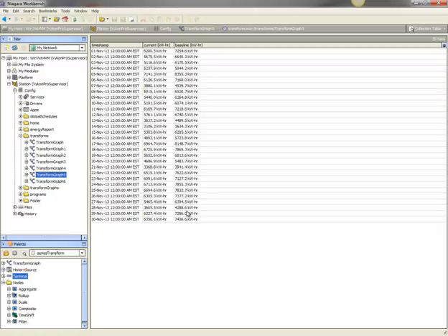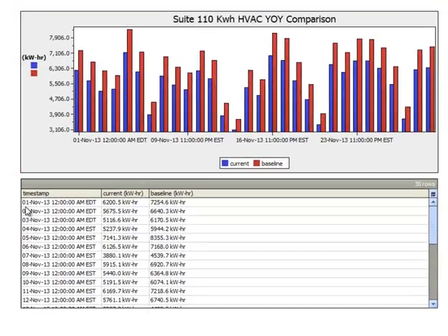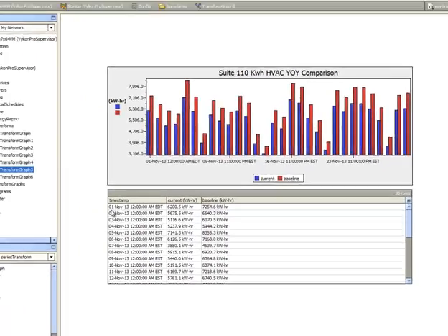Using the right-click Resolve Graph menu selection is an easy way to view the results of the transform graph during the engineering phase. However, it's not typically used for the user interface. It is more typical to embed the results of the transform graph as a table or chart in the PX view for the user interface. This PX view includes both the collection table view as well as the chart view.